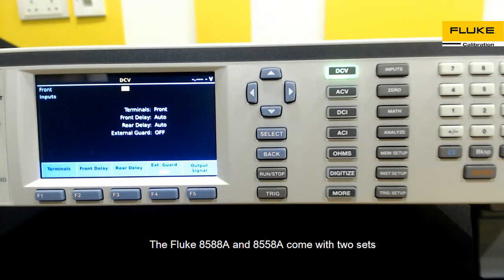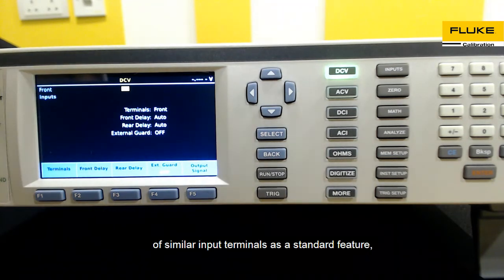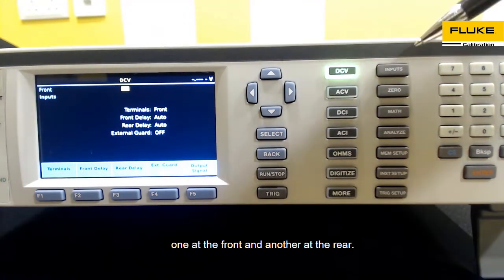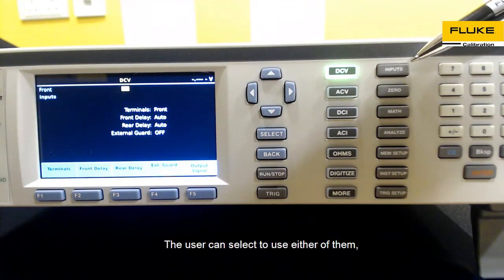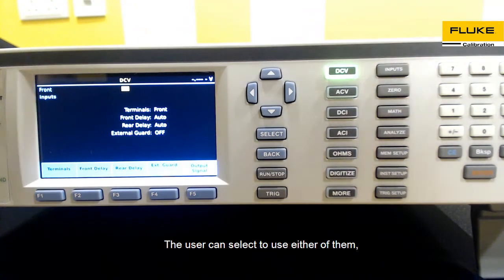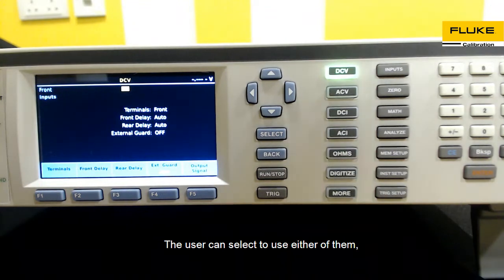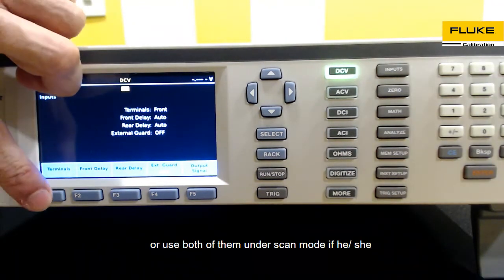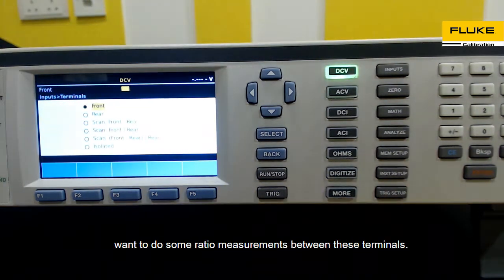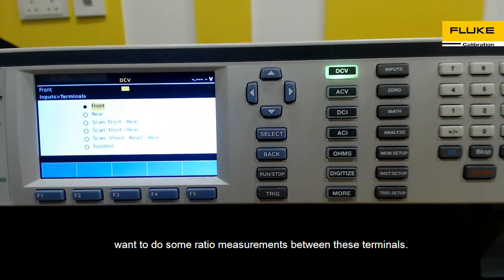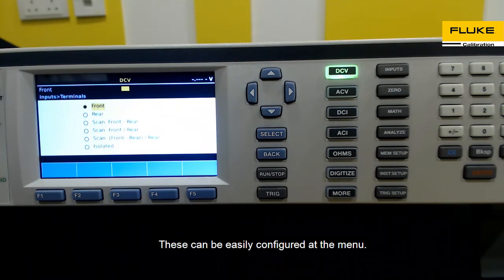The Fluke 8588A and 8558A come with two sets of similar input terminals as a standard feature — one at the front and another at the rear. The user can select to use either of them, or use both under scan mode to do ratio measurements between these terminals. This can be easily configured at the menu.